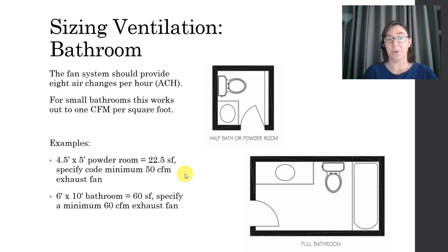For this other small bathroom, it's 6 foot by 10 feet. Therefore, that's 60 square feet. All right, therefore, you would specify a minimum 60 CFM exhaust fan.